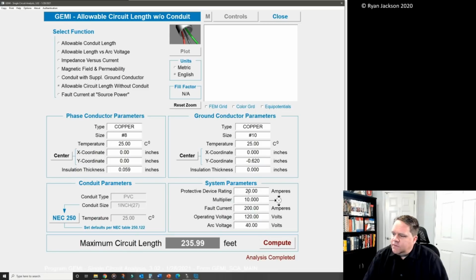And we can play around with all the different values. Let's say I put it on a 30 amp overcurrent device. Then I could only run it 157 feet, which makes sense because I'd have to generate more current in order to trip the breaker quicker. So that is how I would figure out, using the qualified person and not necessarily an engineer, how to increase the size of the equipment grounding conductor when we've increased the ungrounded conductors for any reason besides temperature correction or ampacity adjustment. I know it's kind of a tricky subject for a lot of people, but at the end of the day, I don't know how we could make it easier in the code. I really don't. Some things in the code book are difficult because the topic is difficult, and I think this exception, it's rather surprising the first time you see it in the 2020 code, but I actually think it's a good exception.